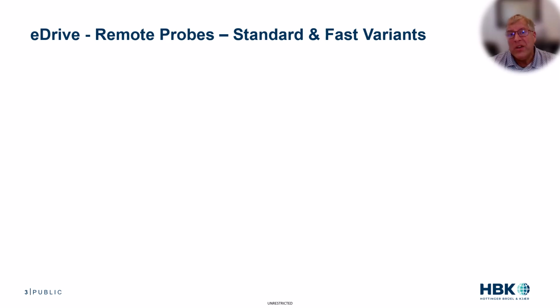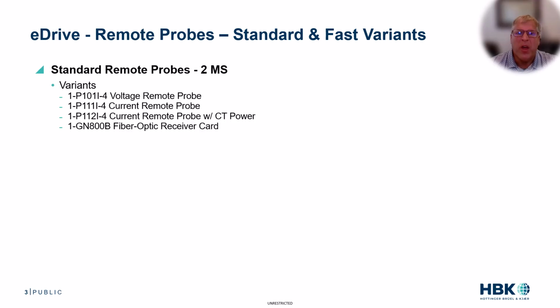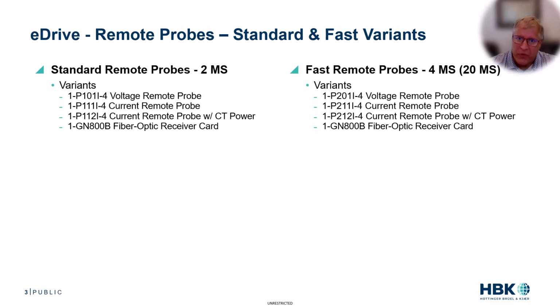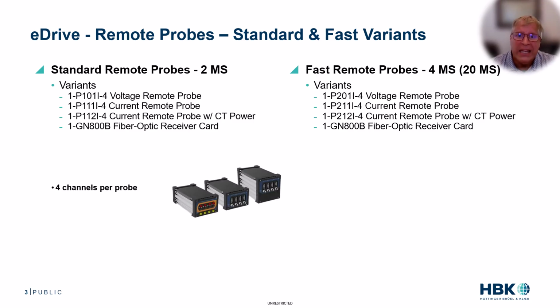Now, as I mentioned earlier, there are two variants of remote probes. There's the standard 2 million samples per second, and there's the fast 4 million samples per second, which can actually record data up to 20 million samples per second. Now, before we address the differences, let's talk about the specifications that are common for both variants, which happen to include 4 channels on each remote probe. There's 3 for the output of the inverter and a 4th for the power source.